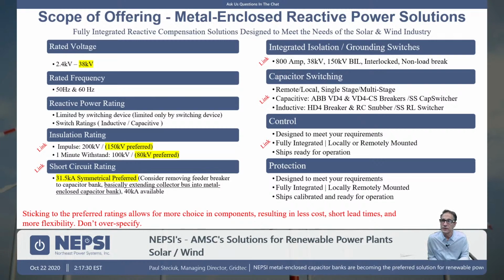System voltage frequency, 50 or 60 hertz, no issue there. The reactive power rating of the equipment is really limited by the switching device. Okay, so when you talk about metal enclosed solution, our limit is based upon the switching device. I think we've gone up to maybe 18 MVAR per stage. We've done systems as large as 75 megavars in a single lineup in the past.